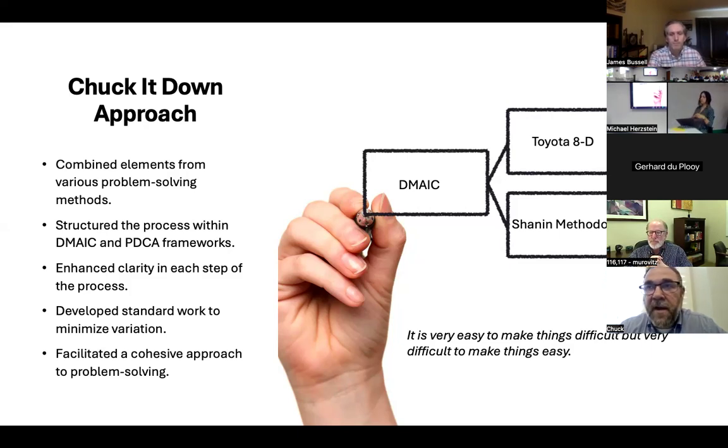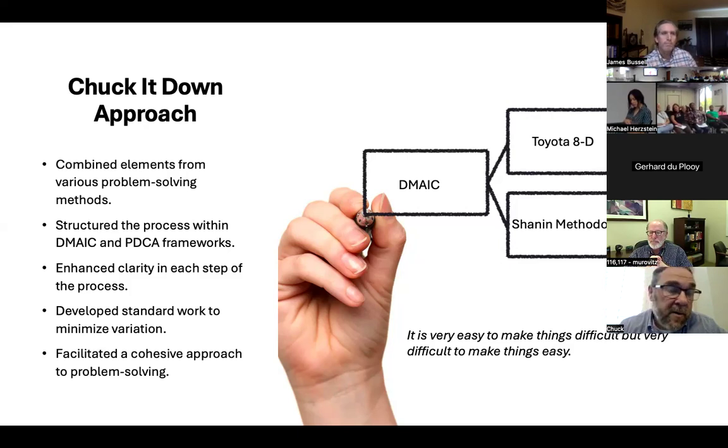So long story short, what we found was that on one of the pieces of equipment in the clean room that cut these down, there was a vent above it, a filter system, that was dropping particles onto the machine. All right, so we looked at that, and particles are falling out of that vent. So the root cause is the vent's dirty? If I'm going to follow my 5 whys, that's not it. But we confirmed that as a cause. I was able to prove, hey, this is a cause, guys. Look, it comes into the machine clean, out of the machine dirty. Anybody here want to object that this machine's not the cause? And I couldn't get that objection. Everybody agreed with me.